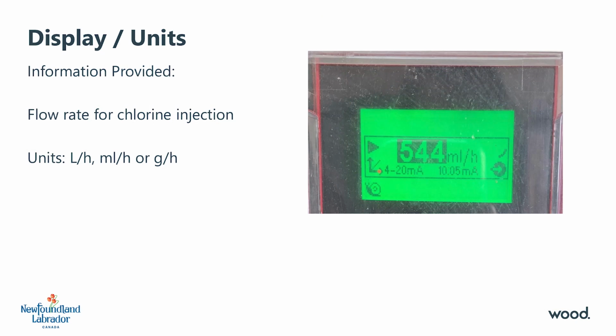There is an existing video titled Hypochlorination available on the Newfoundland and Labrador Water Resources YouTube channel that can be referred to for more information on the preparation of sodium hypochlorite solution. Depending on what type of pump you have, injected chlorine solution flow rate may be provided on a display screen. Operators should know which units are being displayed. Commonly used units are liters per hour, milliliters per hour, or gallons per hour.